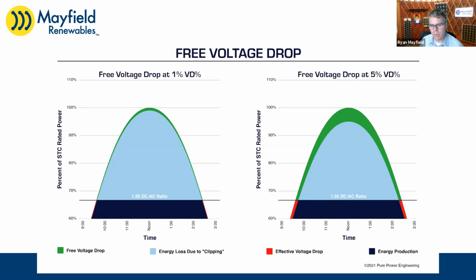It's probably worth pointing out too, not just on the DC side, the losses, but also the longer runs on the AC side, the losses will equate to voltage rise at the inverter, which could then cause the inverters to trip off out of their spec windows. If the inverter's not operating, you're losing everything. So it becomes an even bigger issue, something you have to look at in terms of the design.